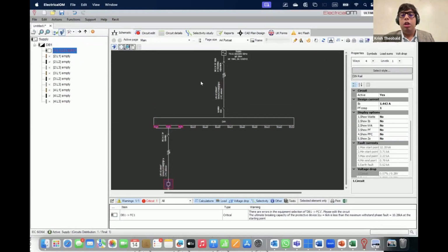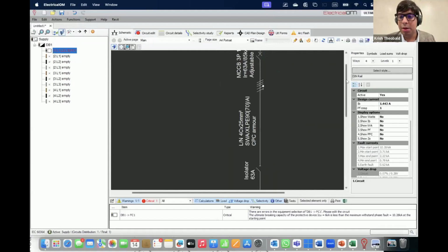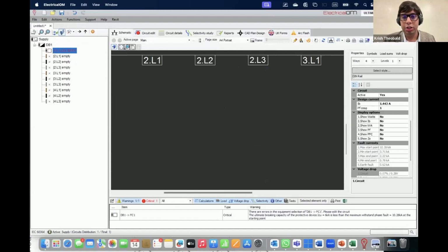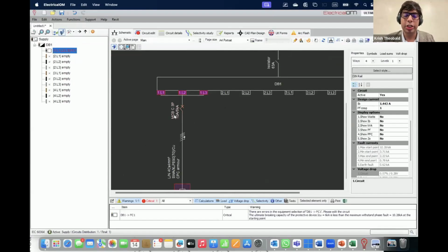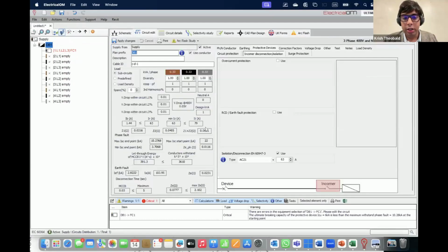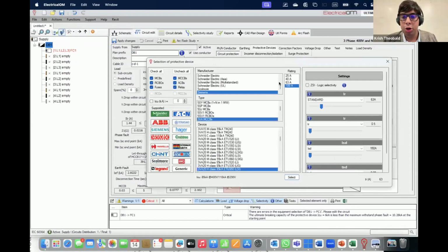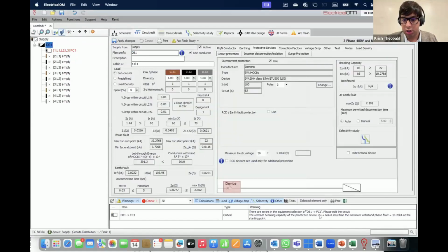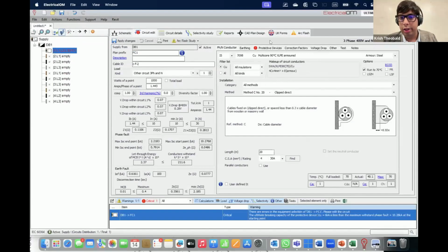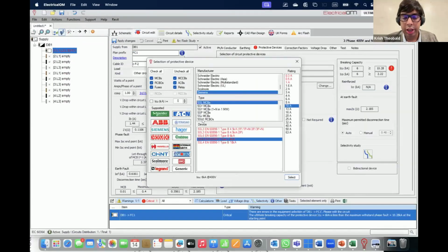Okay. Right. So you see the issue that's come up, which is how the software is quite intelligent. Essentially I've selected a protected device with a 10K breaking capacity, but the software has calculated that at this particular point I actually have a maximum phase fault of 10.2K. So if I now change the protective device, this fault will go away. It's only 6K here, sorry, yeah.